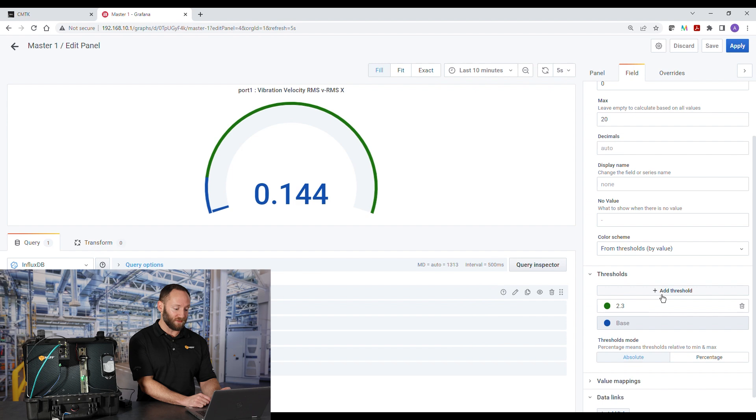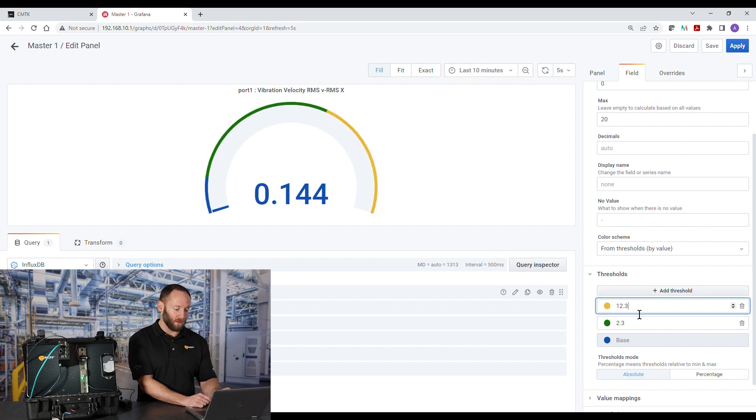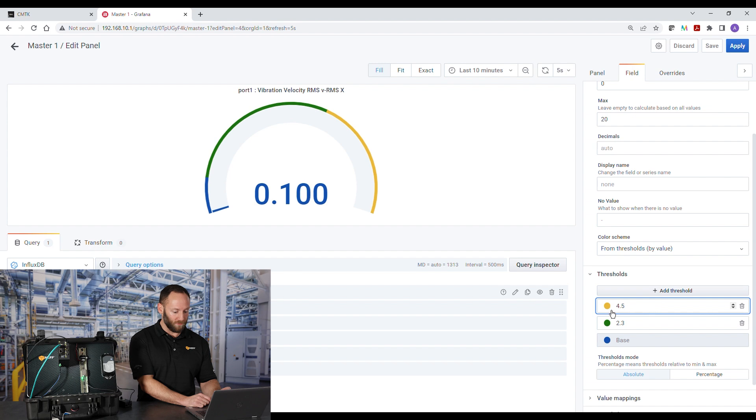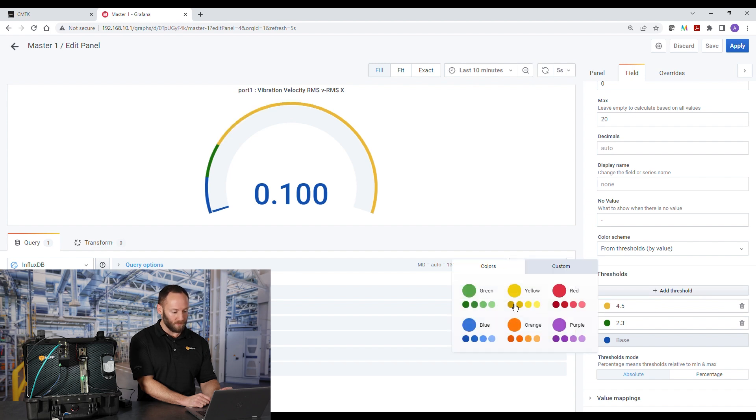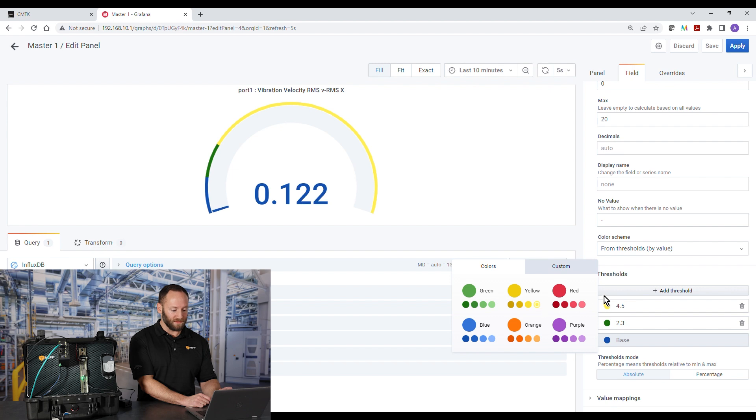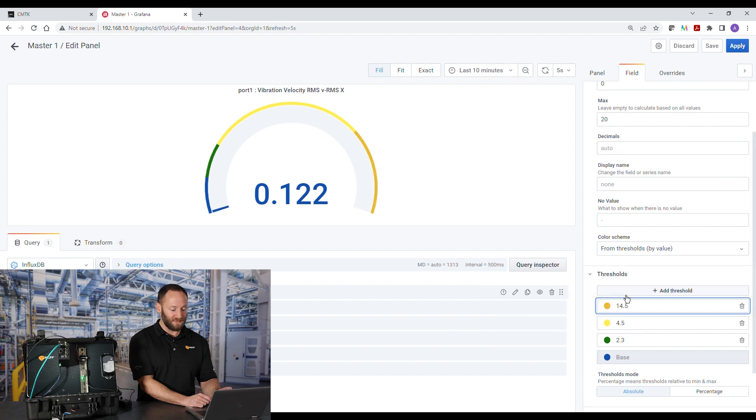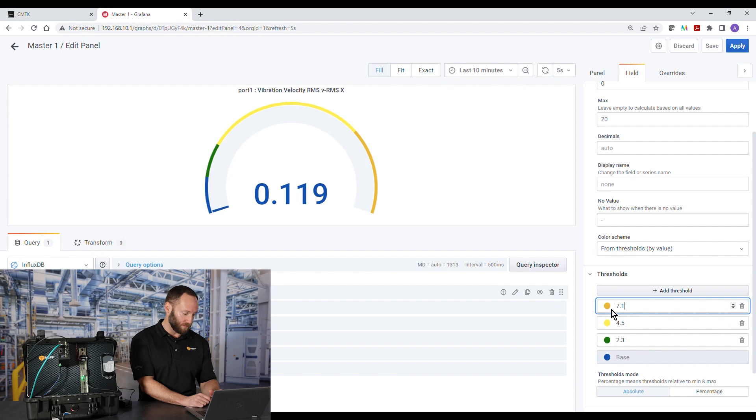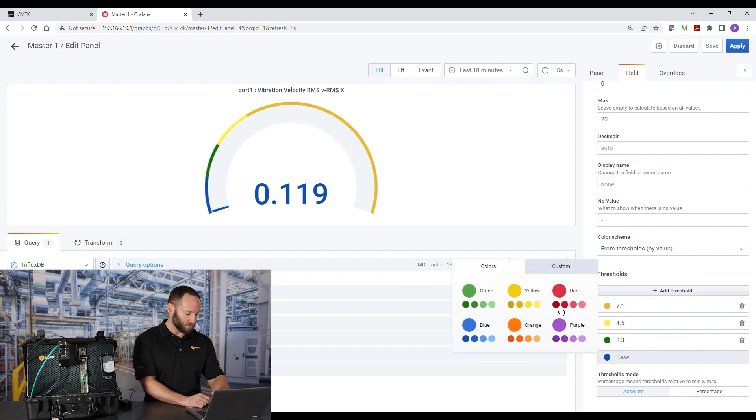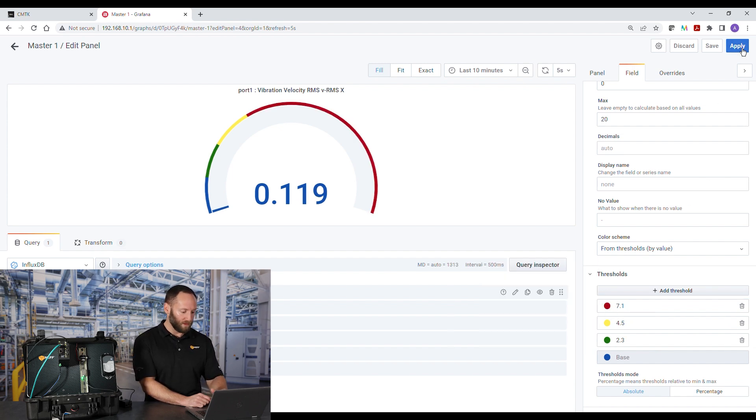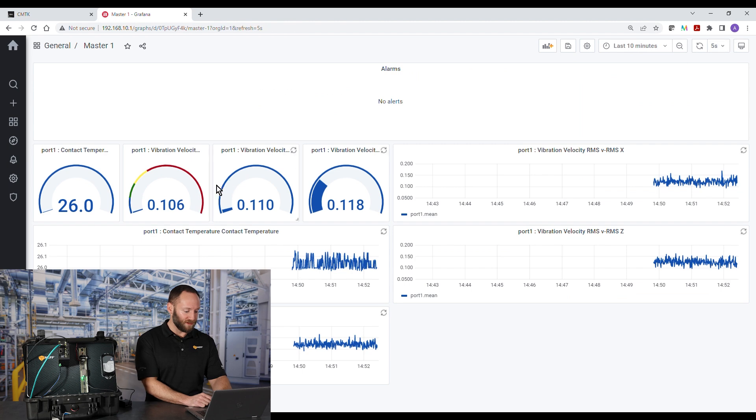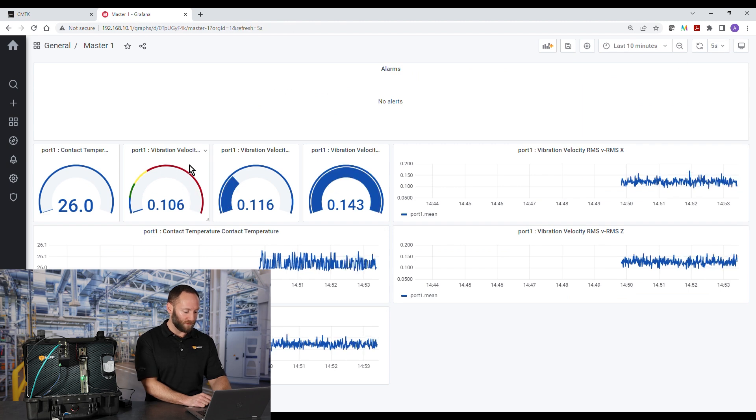Next, we'll select severity zone C, which is 4.5 millimeters per second. And again, we'll click on this little color dot. It'll pop up a menu. We'll select the color yellow. Lastly, we'll select severity zone D, which is 7.1 millimeters per second, the color red. Then we'll hit apply, and we'll see the changes have gone into effect.